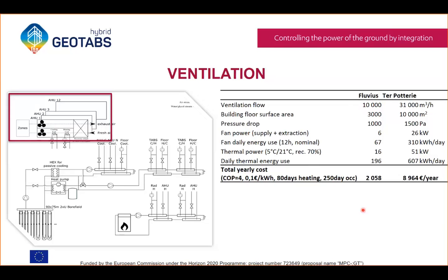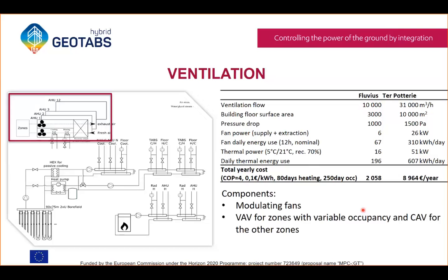So these are substantial, and how can we reduce this cost? Simply by reducing the ventilation flow. But for that, we need modulating fans, which are, I think, most of the time included. But we also need CAVs for the zones with constant occupancy and VAVs for the other zones with variable occupancy. Because by doing so, we can firstly decrease the flow for these different zones, but we can also decrease the pressure head of the fans. So we have two ways to actually reduce the ventilation power.